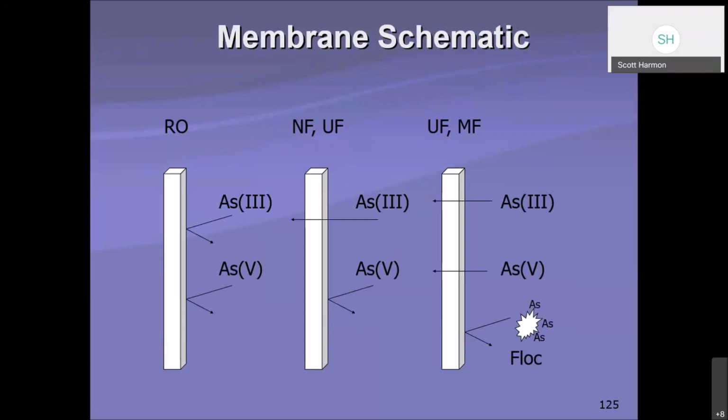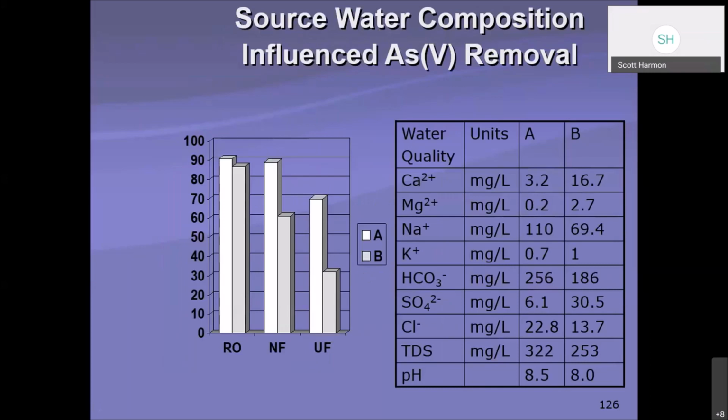So what you would use that for is in combination with your conventional type arsenic removal systems using iron-based coagulants and doing the sedimentation of the iron-arsenic bonded. So if you're using that type of treatment ahead of it, ultrafiltration or microfiltration could be used. If you're not using that type of treatment ahead of it, the other types of nanofiltration, the RO, may be what's used. Again, there's higher costs associated with running these types of filters or pressure type filters.